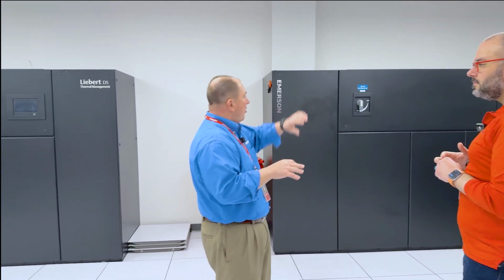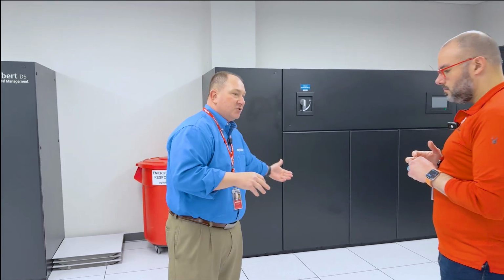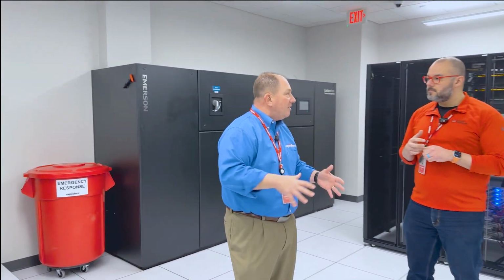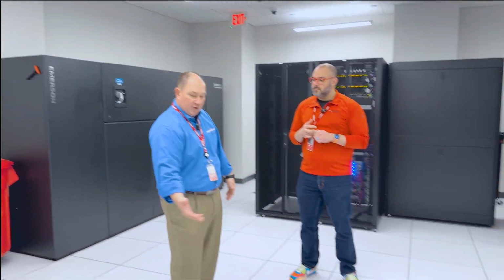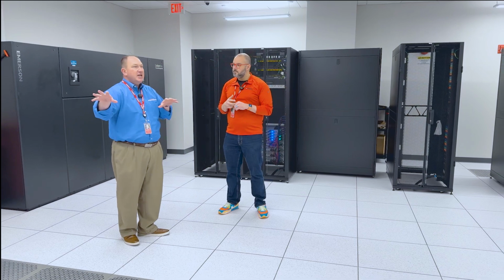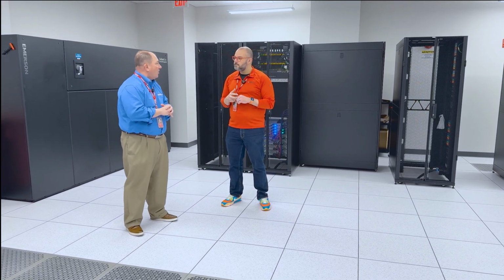So these units take all the hot air through the top and discharge cold air underneath the floor, and that's how we distribute the air. This is all common plenum, so it's pressurized under the floor, and then the air comes through the perforated tiles. We locate these strategically in front of the cabinets to provide adequate cooling to all the cabinets.